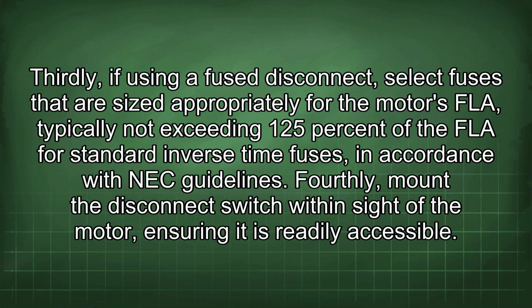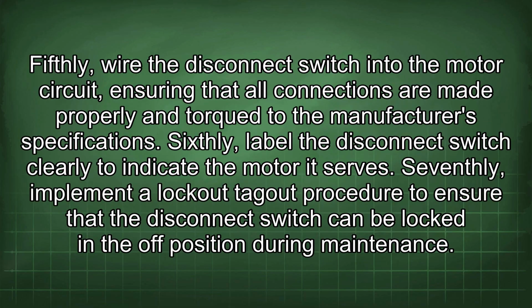Thirdly, if using a fused disconnect, select fuses that are sized appropriately for the motor's FLA, typically not exceeding 125% of the FLA for standard inverse time fuses, in accordance with NEC guidelines. Fourthly, mount the disconnect switch within sight of the motor, ensuring it is readily accessible.